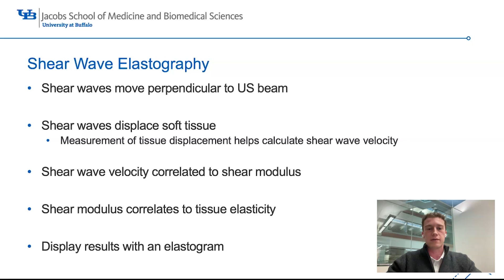So here again is a pictorial of what I just described. In step one, you have a linear ultrasound array, and perpendicular to the acoustic radiation force coming off of the ultrasound transducer, you get these shear waves running perpendicular to that ultrasound beam. It's these shear waves that displace soft tissue through a shear force. Through that displacement, you get a shear wave velocity, which can be tracked and mapped by plugging it into the equation for the shear modulus, where G is equal to the tissue density times the square of the shear speed.